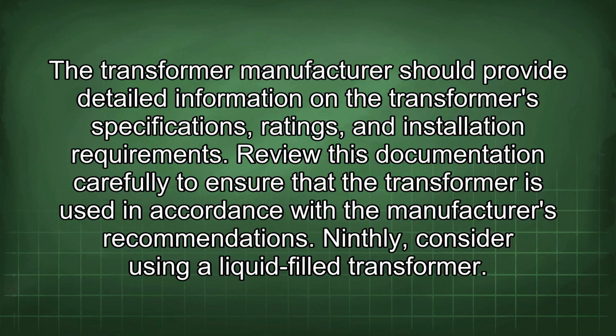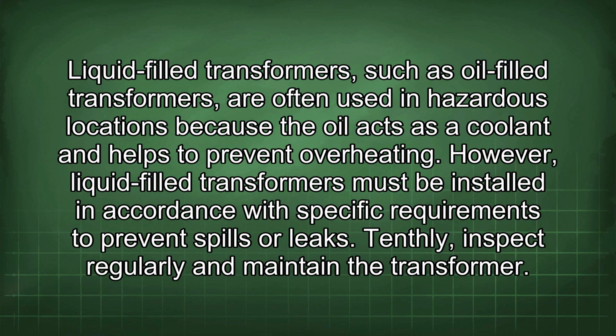Review this documentation carefully to ensure that the transformer is used in accordance with the manufacturer's recommendations. Ninthly, consider using a liquid-filled transformer. Liquid-filled transformers, such as oil-filled transformers, are often used in hazardous locations because the oil acts as a coolant and helps to prevent overheating. However, liquid-filled transformers must be installed in accordance with specific requirements to prevent spills or leaks.